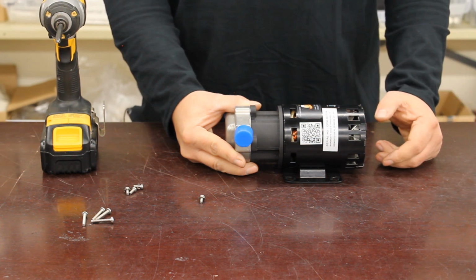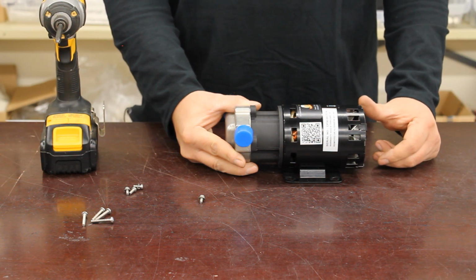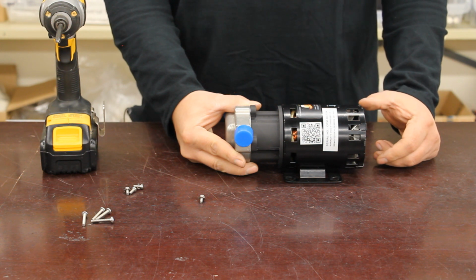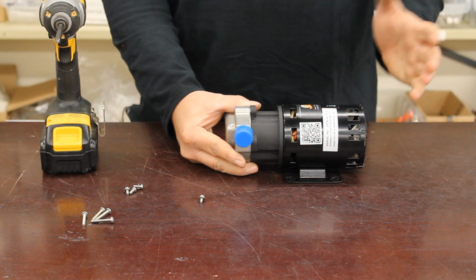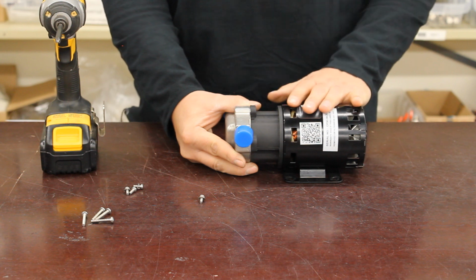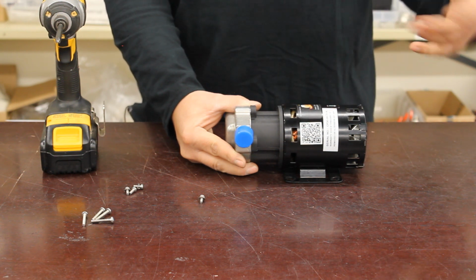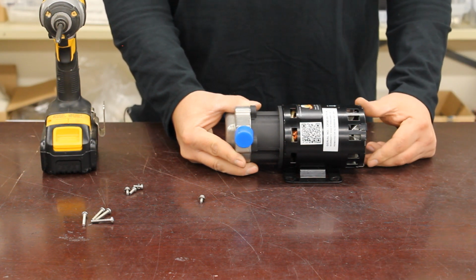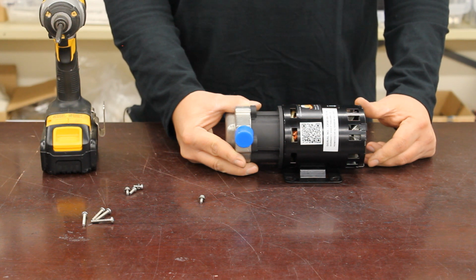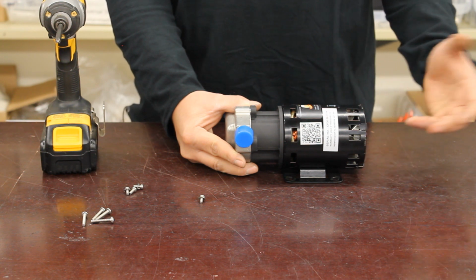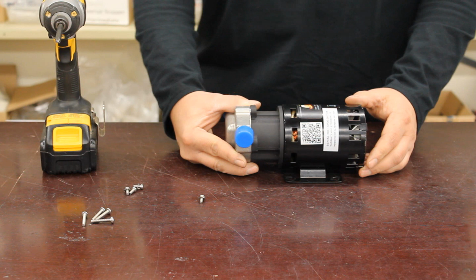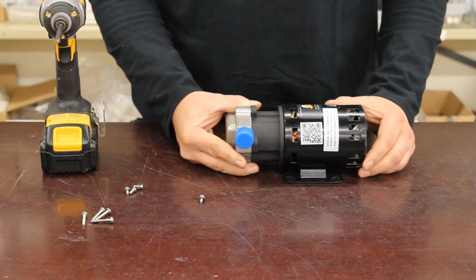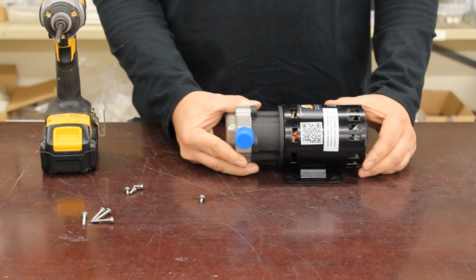Again, make sure that the thrust washers are not fully worn out and causing the impeller to hang up. You may have an issue with the magnetic coupling. This has been diagnosed as a problem with the cup magnet's magnetism, such as the magnet losing magnetism, which is not totally impossible, but it's most likely not the case.